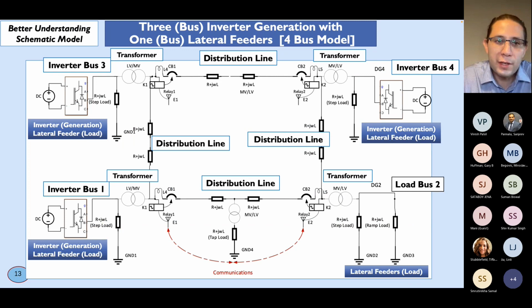So we have basically a 4-bus grid where we have 3 inverters and load, and in the 4th bus just a load with lateral feeders. We call it a 4-bus model because we have the operation in low voltage, like it should be done in a household or in a small neighborhood. And the distribution is done in low voltage as well, or medium voltage, depending on the country or the norm utilized.